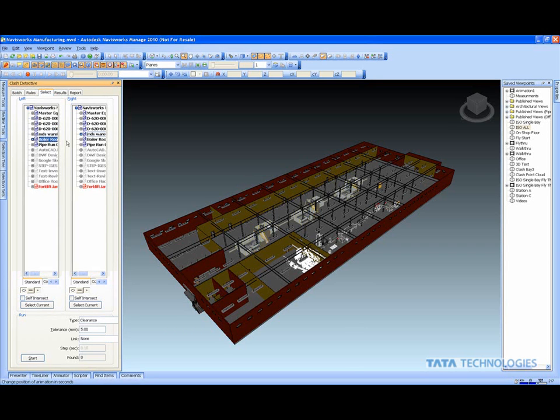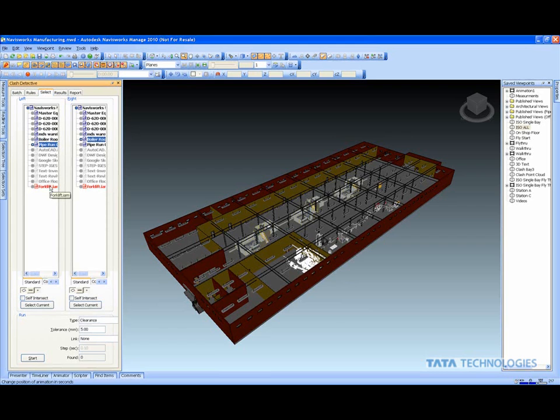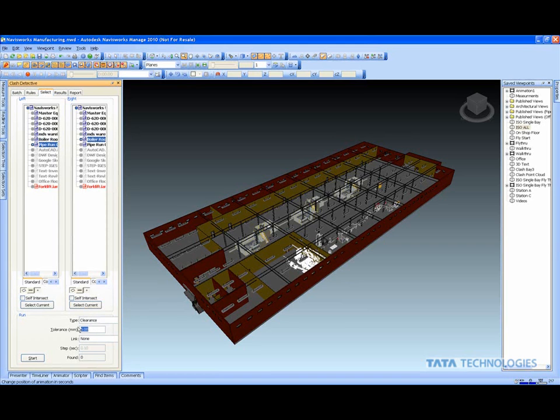Here I'm going to do my pipe runs with my boiler room, taking them out of my selection sets. I'm going to make sure I include the point cloud data, set up my clearance, and do a 5mm check. Just as quickly as we did our hard clash, Navisworks is going to produce our soft clash information.